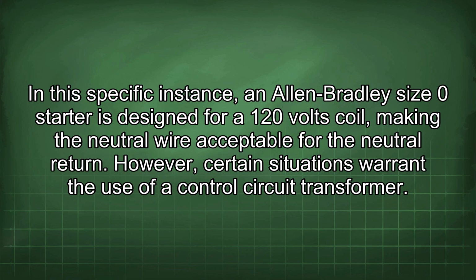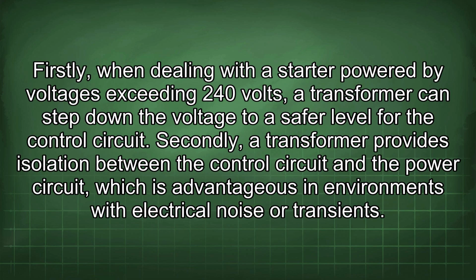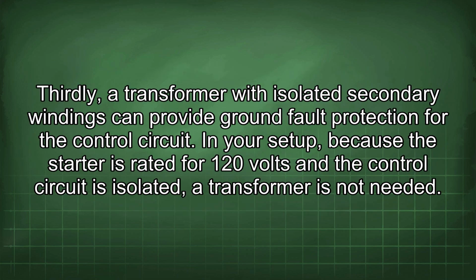However, certain situations warrant the use of a control circuit transformer. Firstly, when dealing with a starter powered by voltages exceeding 240 volts, a transformer can step down the voltage to a safer level for the control circuit. Secondly, a transformer provides isolation between the control circuit and the power circuit, which is advantageous in environments with electrical noise or transients. Thirdly, a transformer with isolated secondary windings can provide ground fault protection for the control circuit.